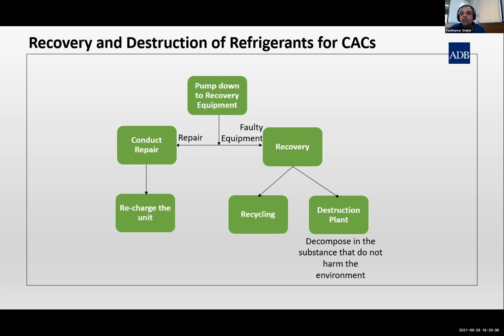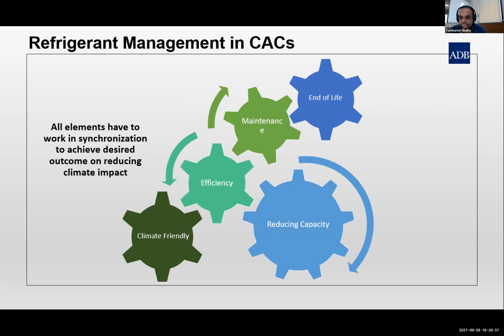But if the equipment is faulty, then you put it in a recovery unit and you either do recycling, or if the machine is not functioning, if it has reached the end of its life, then you take it to the destruction plant, and you have to have a system in place where you decompose it into substances that do not harm the environment. So this recovery and destruction of refrigerant is very important to minimize the climate impact of refrigerant.